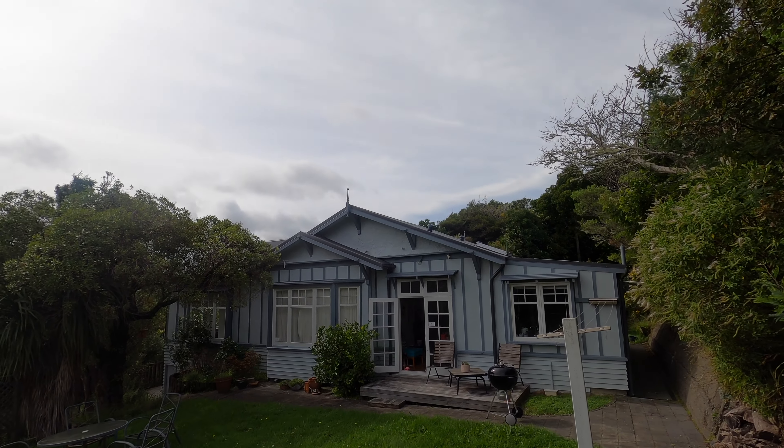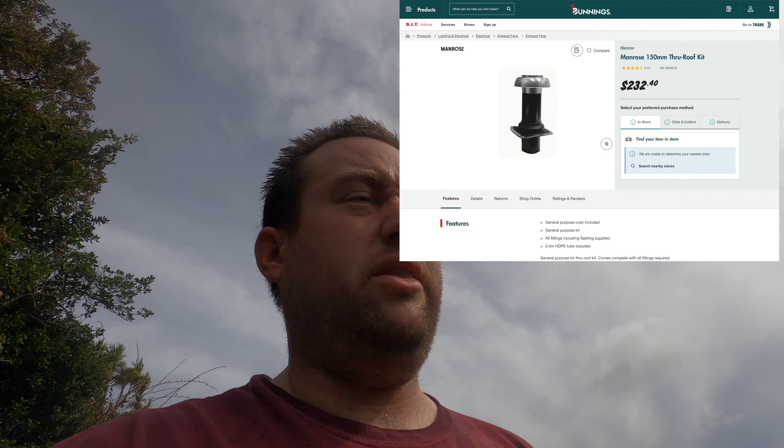That weird angle it's worked in — seems fine. They're pretty cheap vents to be honest, pretty cheaply made, but they're really expensive — frankly, everything in New Zealand is. The crazy thing is the cheap tubing we ripped out, that failed after 5 years, it's $22. That new duct I brought — the flexi-duct was $44 delivered off Trade Me, which is like our eBay — so not even wholesale price. For the sake of what's maybe $10 wholesale, why would you put such a cheap tube in for an intake? Trades here tend to be pretty cheap-scale on a lot of materials. And the same thing is, if they had put in the rigid from day one it wouldn't have collapsed, and it would probably live for a full 15-year lifespan. So I guess that would be the old argument: do it once, do it right. Hopefully I've now done it right — but time will tell, I guess.